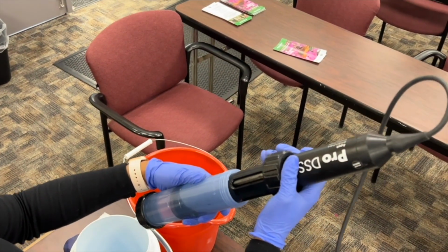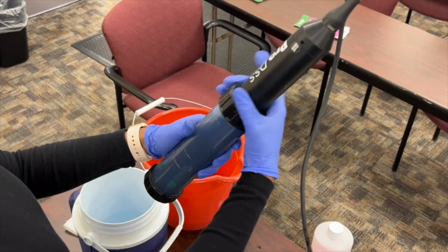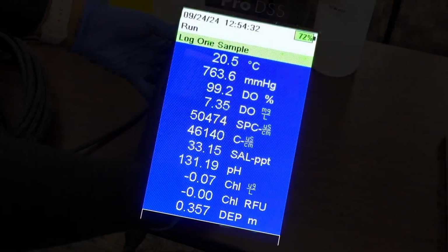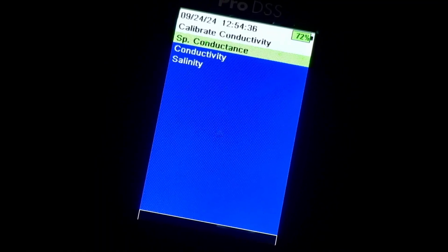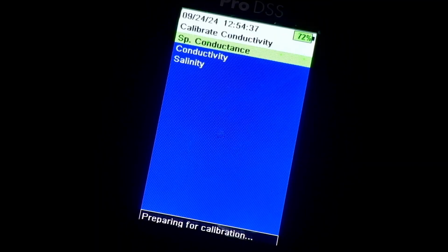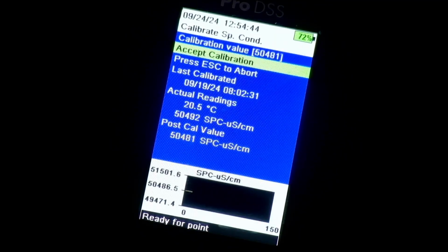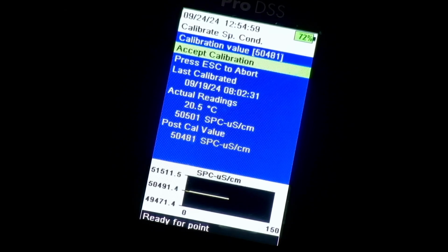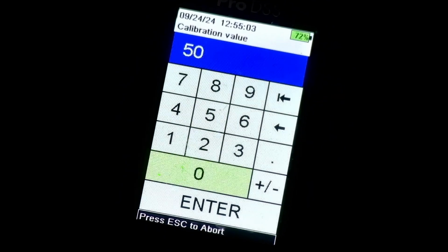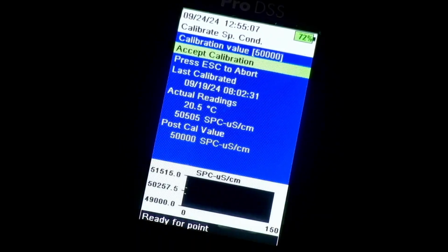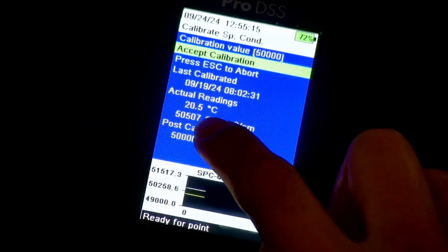Then insert the sonde slowly at an angle. Gently rotate or move the sensors up and down to remove any air bubbles that may be trapped in the conductivity cell. When ready, press the cal button, select conductivity, and then specific conductance. Next, you will need to change the calibration value to 50,000 microsiemens. Allow the sensor to sit for at least 40 seconds for temperature equilibration, and then use the value under actual readings to record the pre-calibration concentration on the calibration sheet.